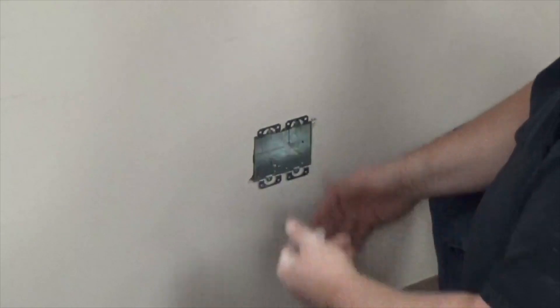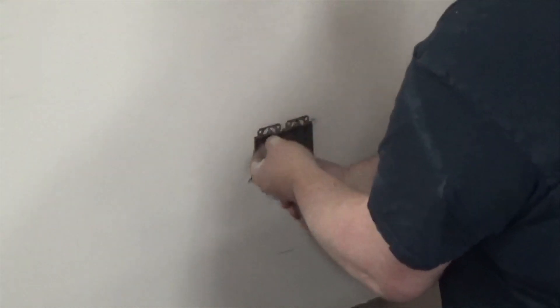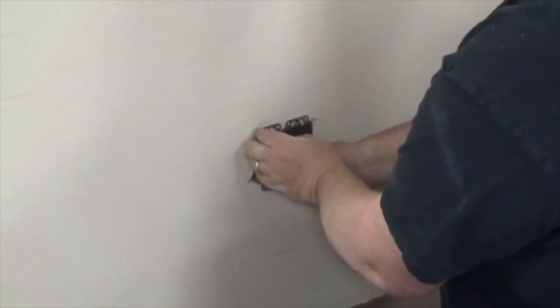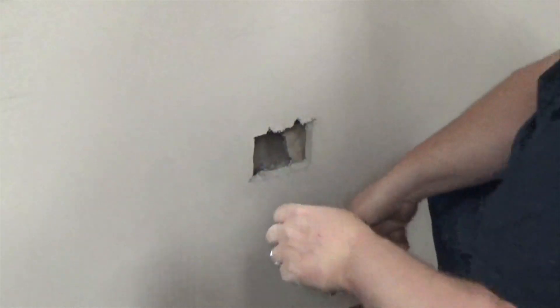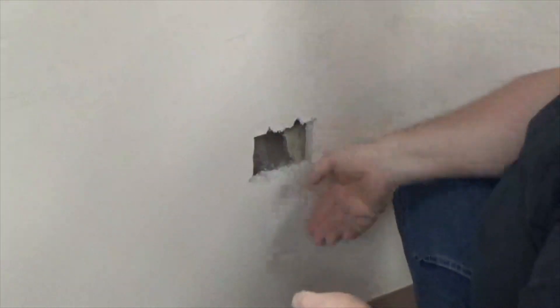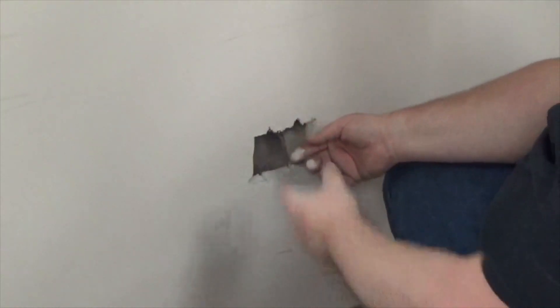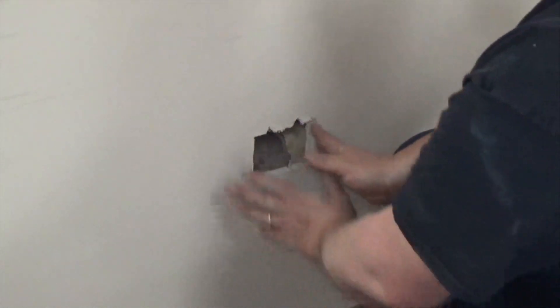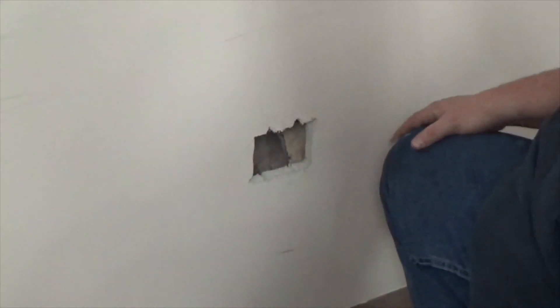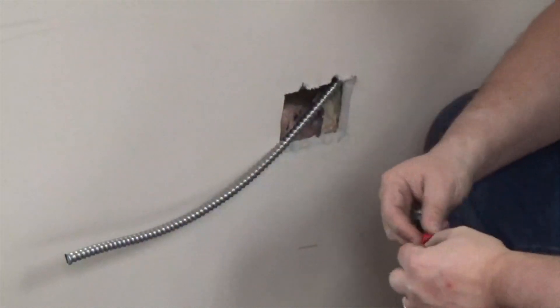So using MC cable, we have to do something first. We actually have to take the box out. We'll take the box out. And then what we'll do is, what we'll do is we'll snake the wire down. And then what we'll have to do to connect it, we have to actually put a connector on the box. So we'll pull the wire down. We'll put the connector on. We'll slide it up and then we'll slide the box in. And then I'll show you how to strap it with Madison straps.